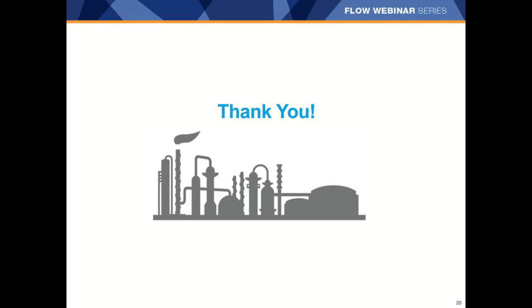Somebody's asking, does Emerson offer flow totalizers or integrator functions in the transmitters? Yes, we have multiple totalizers, especially on some of the newer transmitters like the Model 5700 that Robin was mentioning. We have the option to set up more than one totalizer so you can do a forward or reverse totalizer, but all of our transmitters do have a general totalizer function. Since they're bidirectional, we have the opportunity to do backwards and forwards totalizing. Right, on some of the transmitters we can do that for sure.